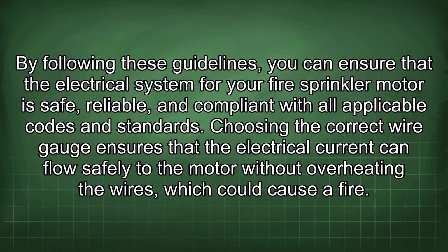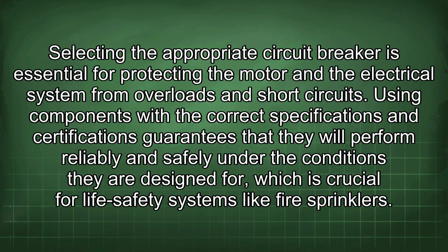Choosing the correct wire gauge ensures that the electrical current can flow safely to the motor without overheating the wires, which could cause a fire. Selecting the appropriate circuit breaker is essential for protecting the motor and the electrical system from overloads and short circuits. Using components with the correct specifications and certifications guarantees that they will perform reliably and safely under the conditions they are designed for, which is crucial for life safety systems like fire sprinklers.